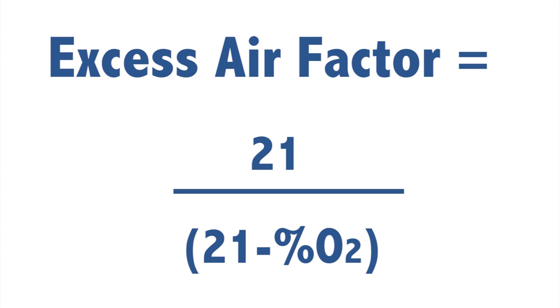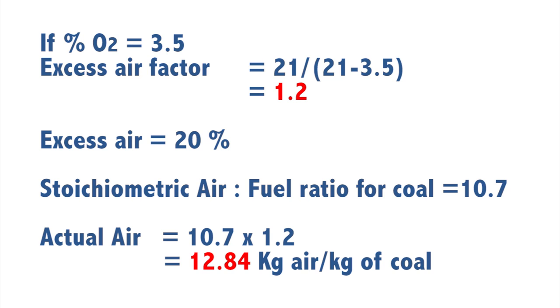Now that excess air could be 15%, it could be 20%, it could be 25% — that depends on the kind of fuel and the kind of boiler. The excess air and the quantity of oxygen present in the flue gases have a direct correlation. There is a formula that links both of them together, and the formula is: excess air = 21 / (21 − O₂). An excess air factor of 1.2 indicates that 20% excess air is present. Therefore, knowing the oxygen percentage in the flue gas is the first stage.